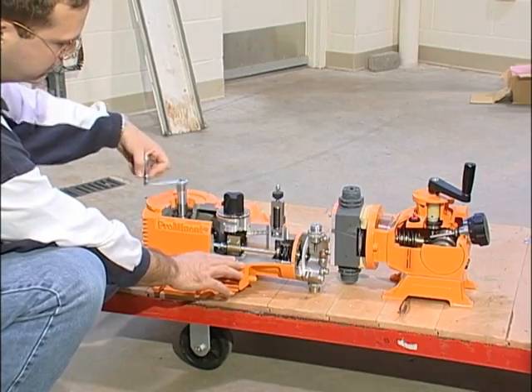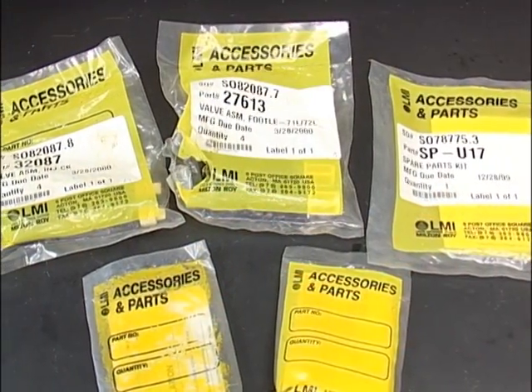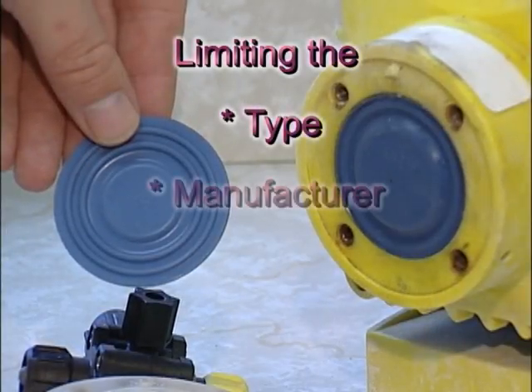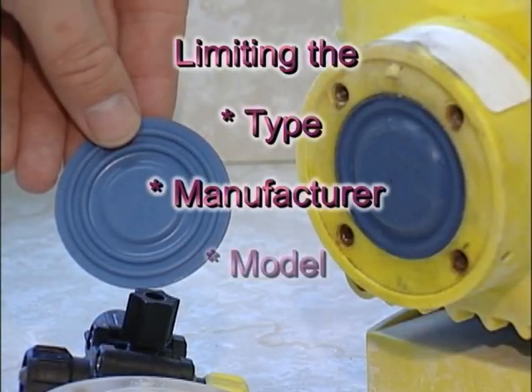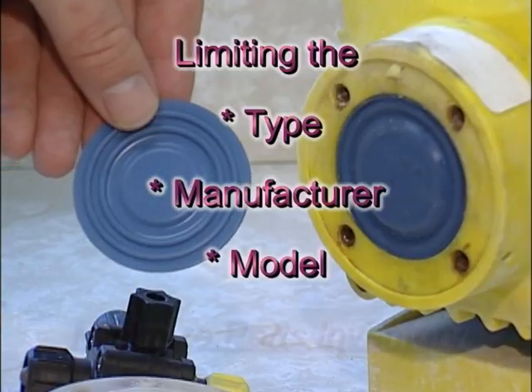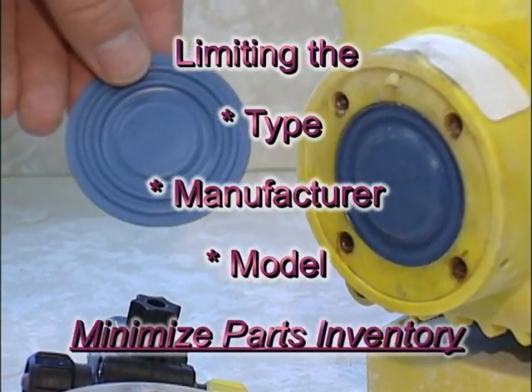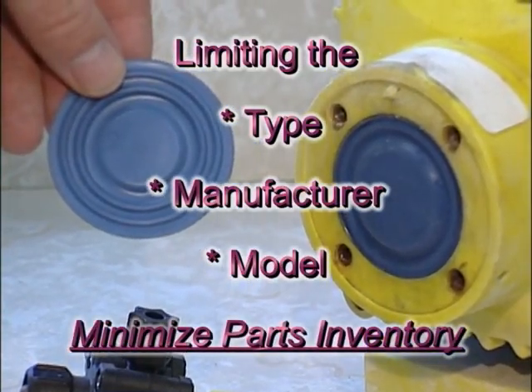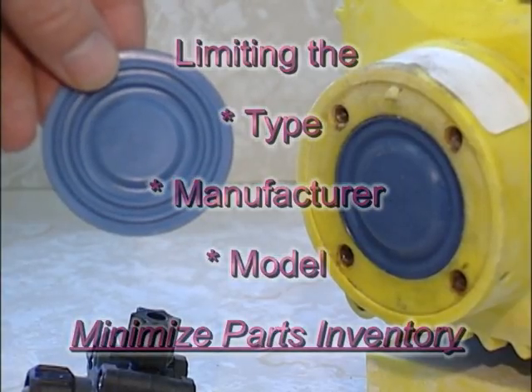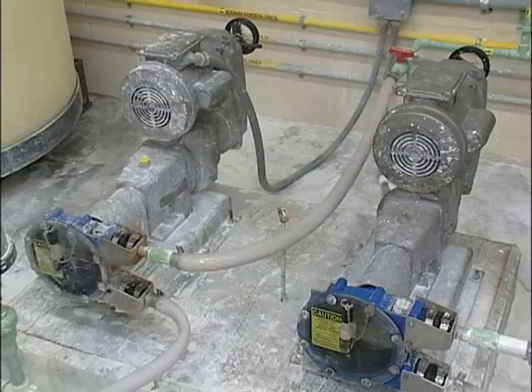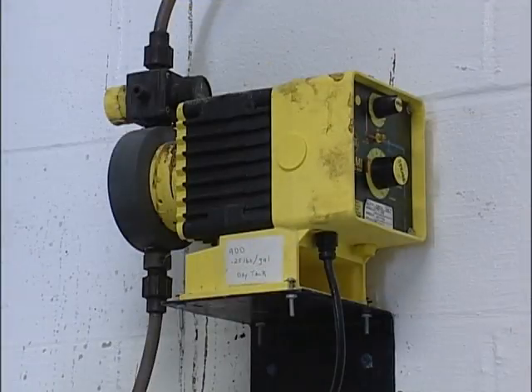Another consideration in purchasing a pump is the parts inventory you should carry. Limiting the type, manufacturer, and model of pump where possible allows you to minimize the parts inventory required to ensure continuous operation of the chemical feed pumps. Two popular pump types are peristaltic pumps and diaphragm pumps.